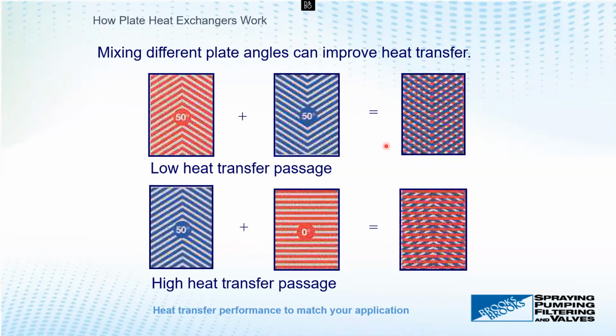This is true for anything, and you can change it over time. Should your process change and you want to extract more heat, and can afford more differential pressure, we can slide in a new or different plate pack. That's the beauty of plate and frame exchangers—as things change, it's just a plate pack, so we can grow and change with whatever you're doing. It's not a commitment, other than that once you get the plate pack, it will only do what it's supposed to do based on its corrugations and differential pressure.